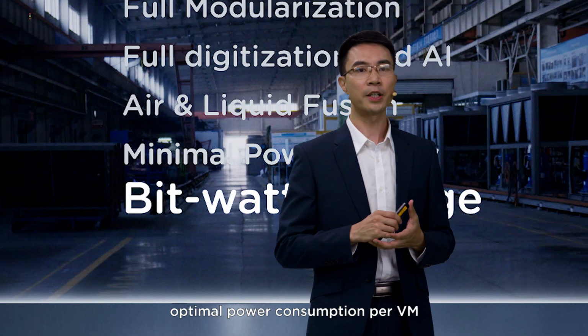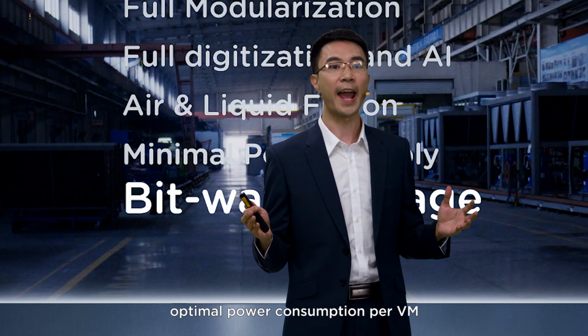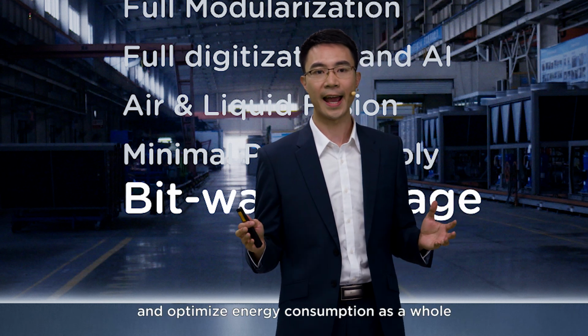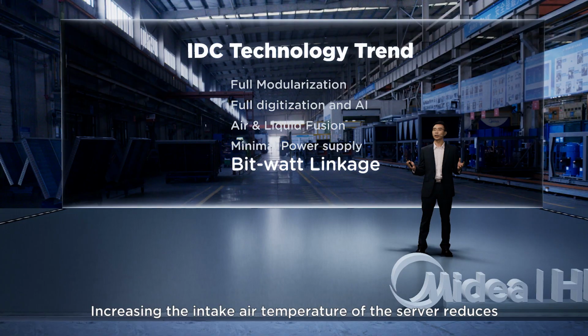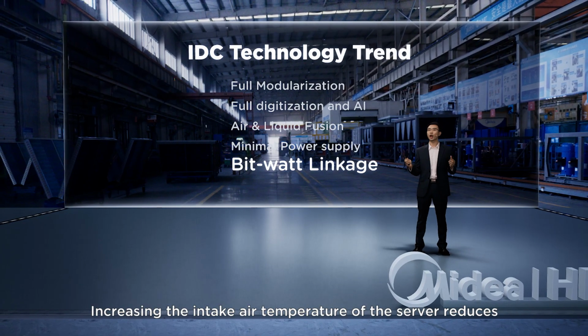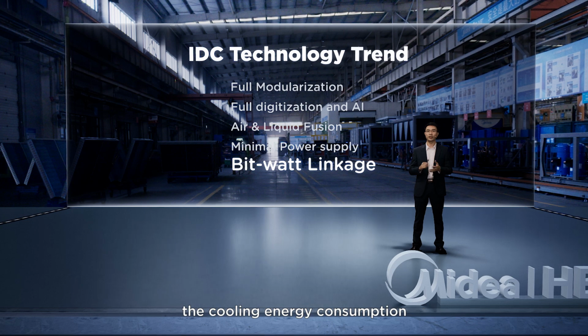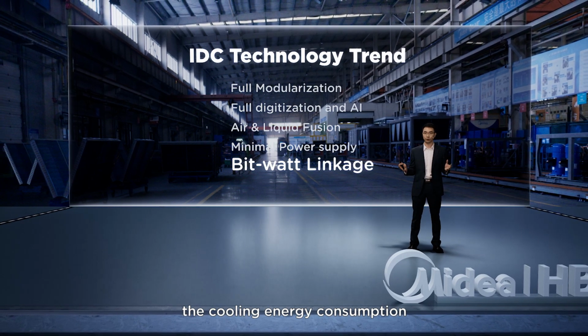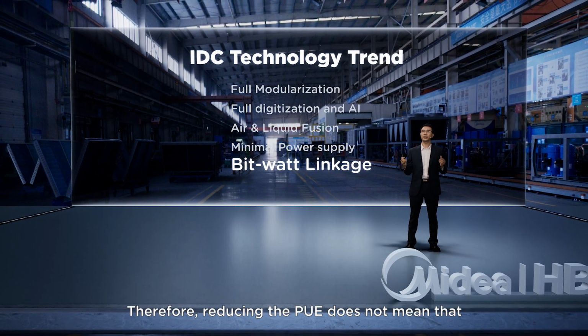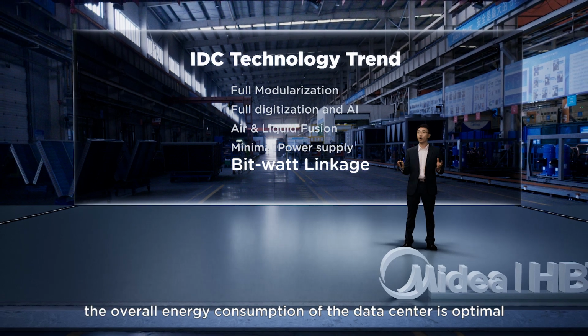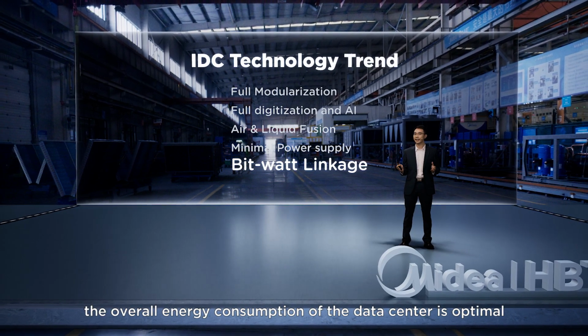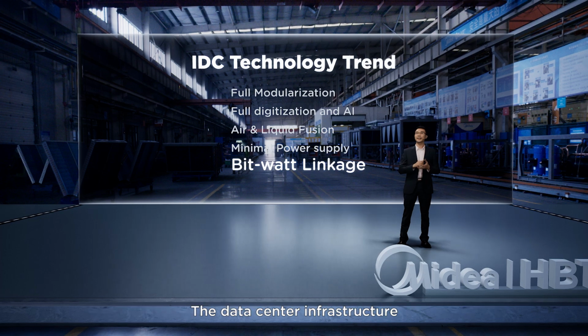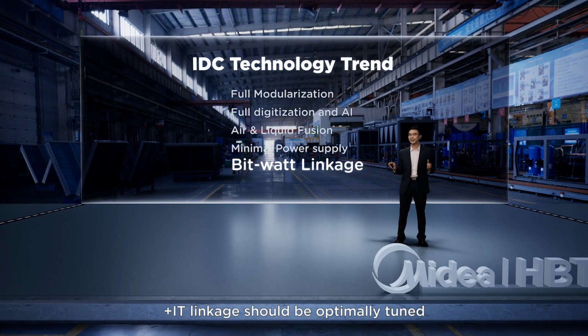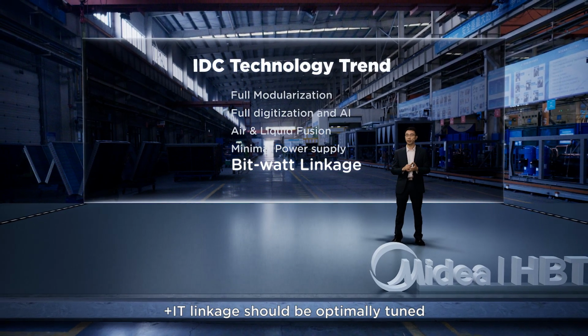Bit-watt linkage enables optimal power consumption per VM. Data centers should evaluate and optimize energy consumption as a whole. Increasing the intake air temperature of the server reduces the cooling energy consumption. Therefore, reducing the PUE does not mean that the overall energy consumption of the data center is optimal. The data center infrastructure and IT should be optimized together.